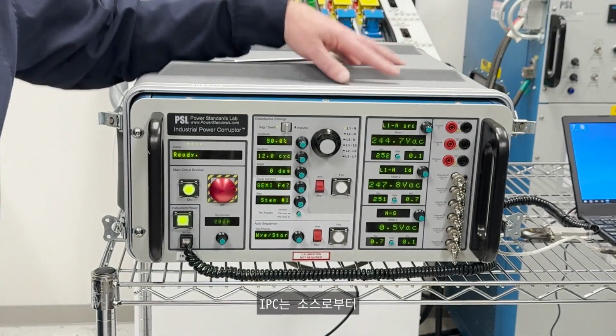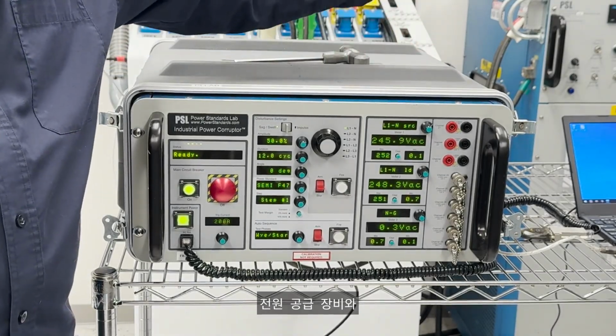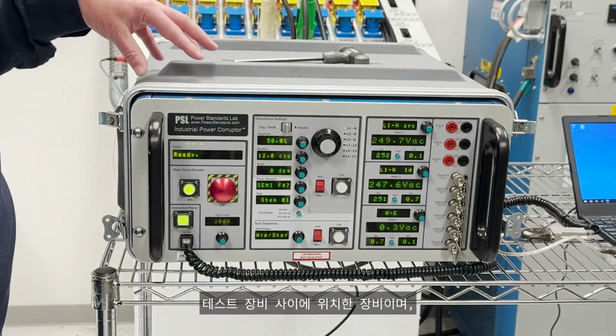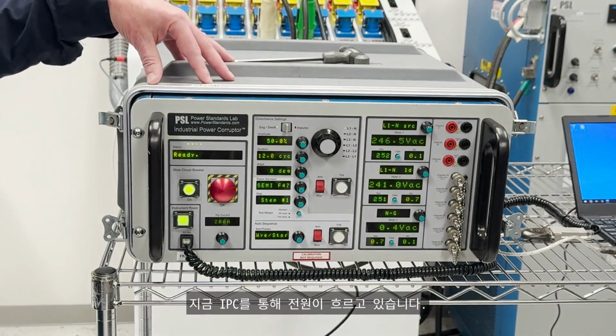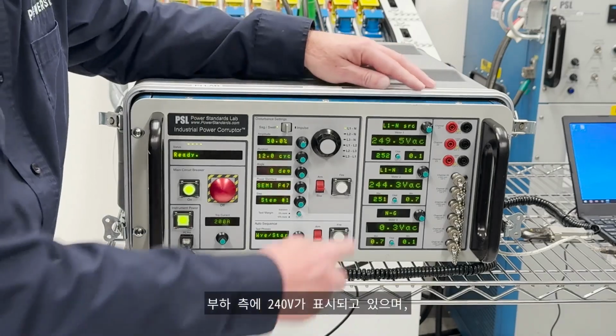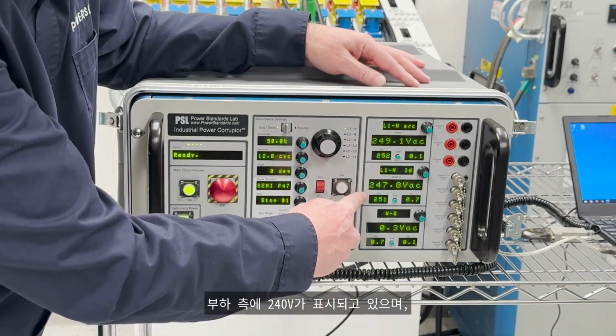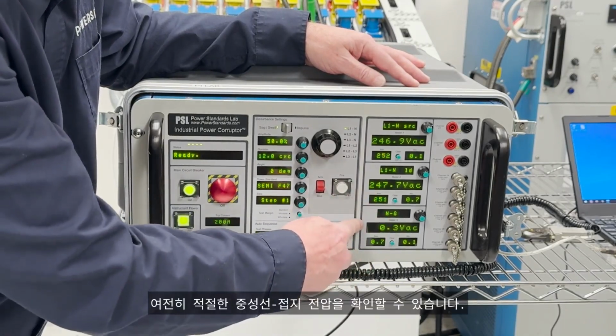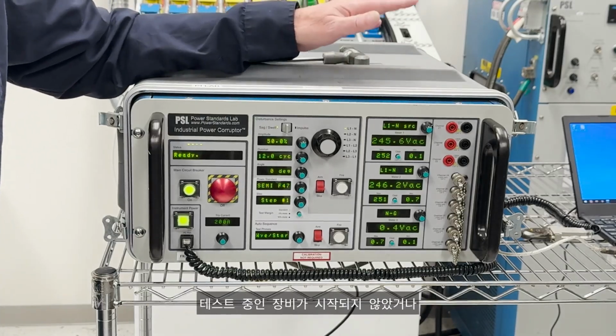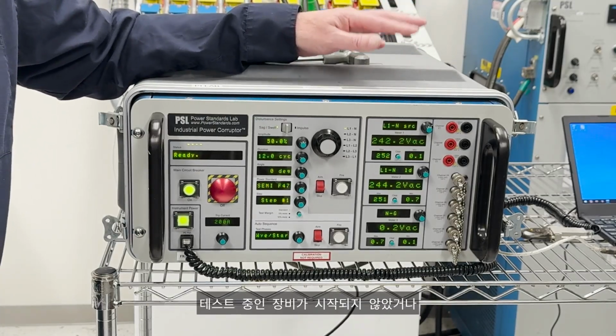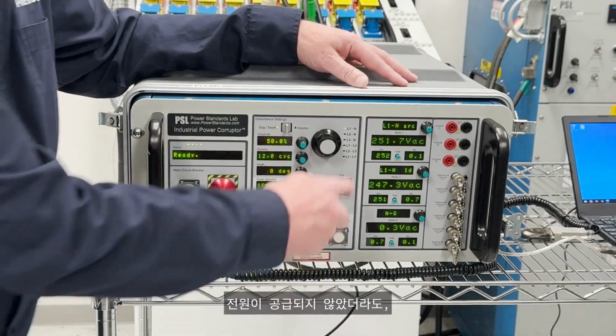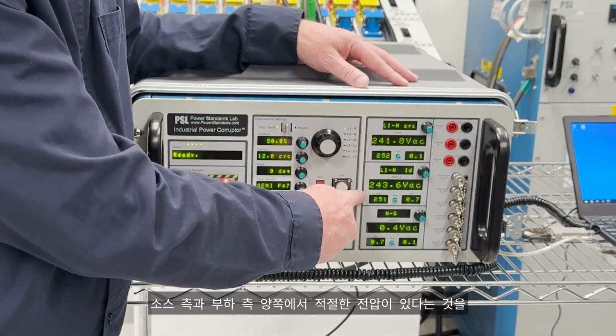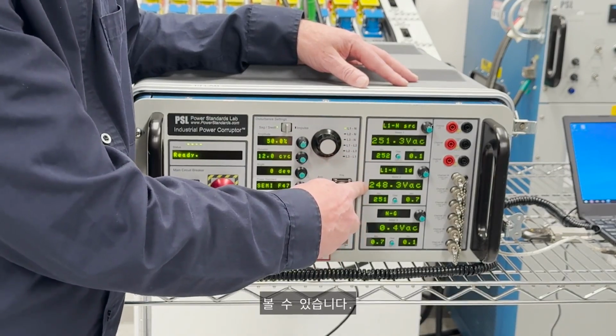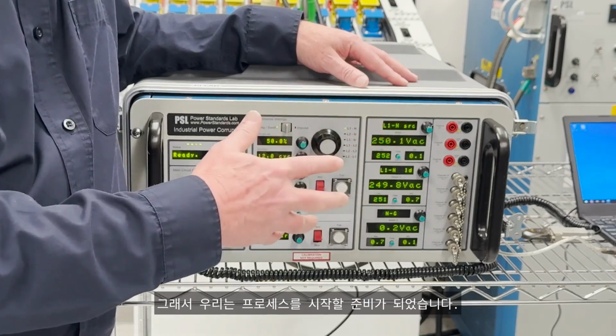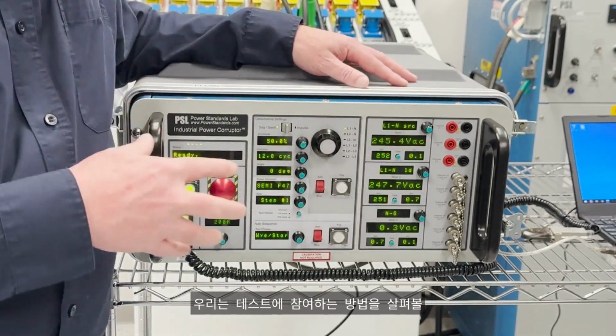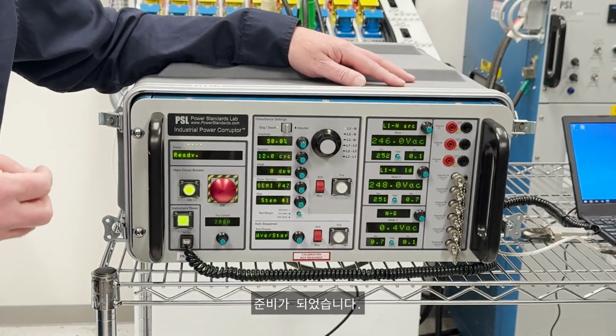So the IPC, that is the series piece of equipment between power supply from your source and the equipment under test, is now passing through the IPC, and you see here that now on the load side we have 240 volts. We still have a sensible neutral to ground. Even if your equipment under test is not started or you haven't energized it, we can see now that there's an appropriate voltage on both sides, both the source side and on the load side. And so we're ready to start the process. We're ready to start looking at how we can engage in a test.